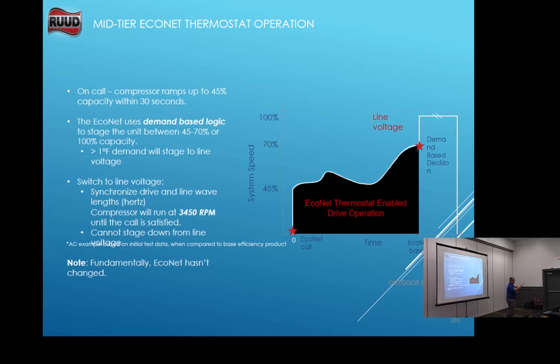That's why we have to lock it into charge mode when we put our gauges on it, so we have a fixed speed, okay? But in between there, it will run at 45 to 70% modulating and maintaining that temperature to within 1 degree if it's on an EcoNet. After a certain time base, like 12 to 15 minutes or 20 minutes max at low speed, if it hasn't reached desired temperature, it would drop off of the inverter drive and go to that contactor and capacitor and go to line voltage, to 100%.